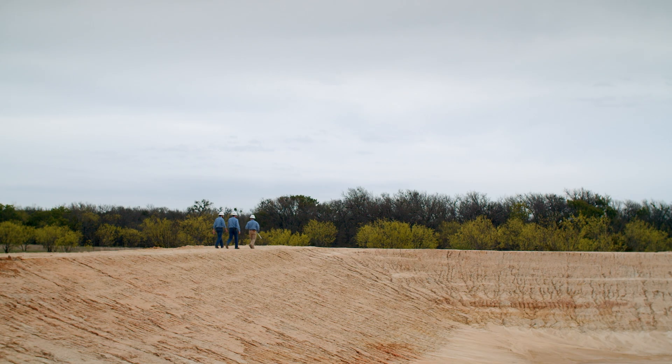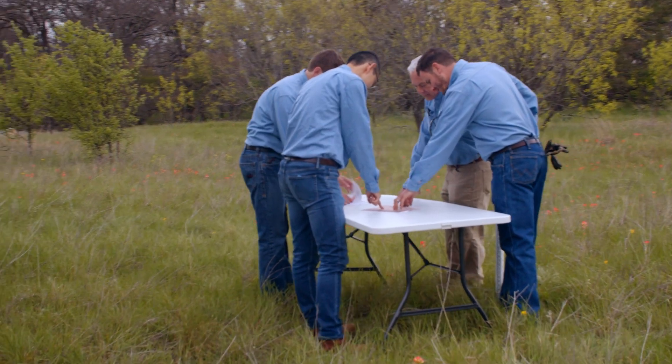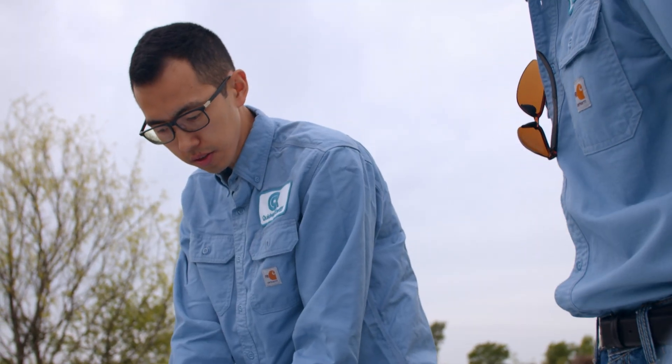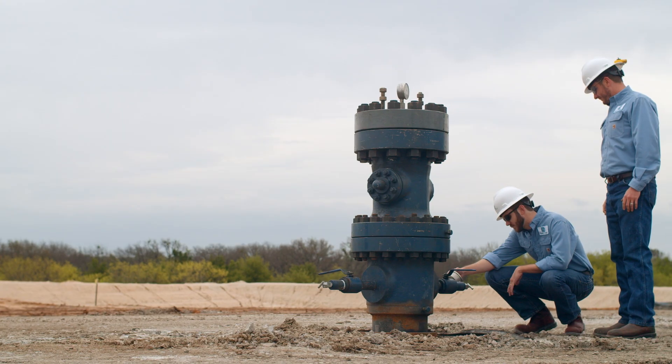For pumped hydro storage, the majority of the cost is building the dam and constructing on the side of a mountain. With Quidnet's subsurface geomechanical pump storage, we take that cost and bring it down about an order of magnitude. The Quidnet facility essentially involves a surface pond, a mechanical room, and a well.